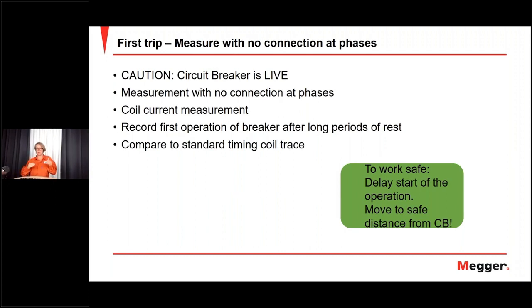But the first operation we do, we normally don't check. We make an open to be able to disconnect and ground to do the measurements. But here we can measure that first one. So we really know the status of the circuit breaker before we got to the station. And you, of course, do comparisons a lot here as well. You want to compare with standard timing coil trace.